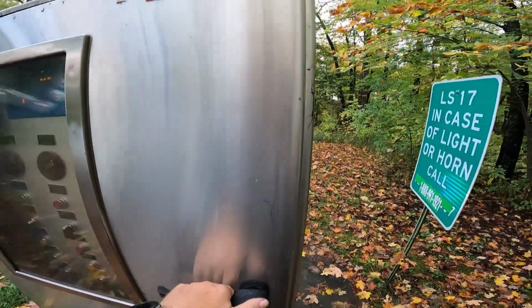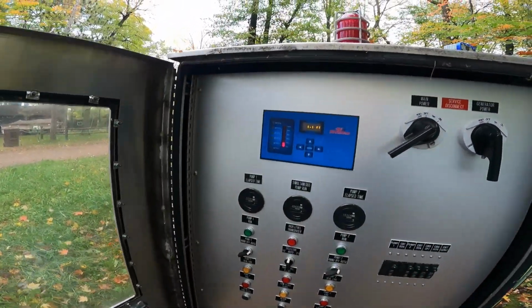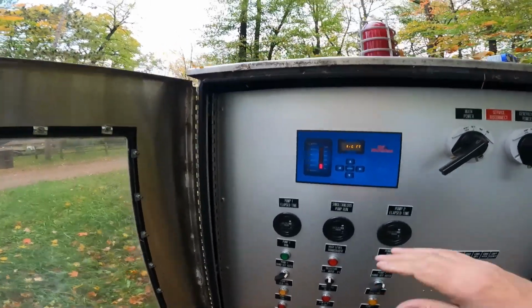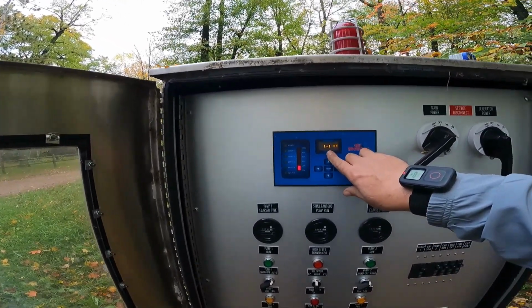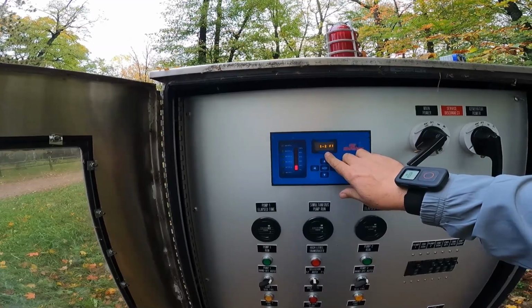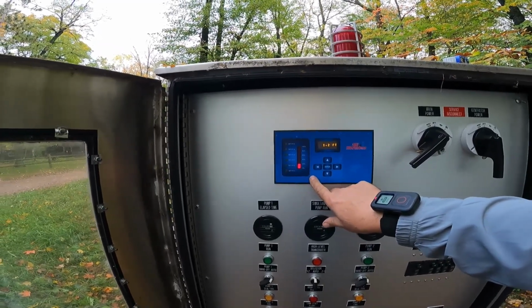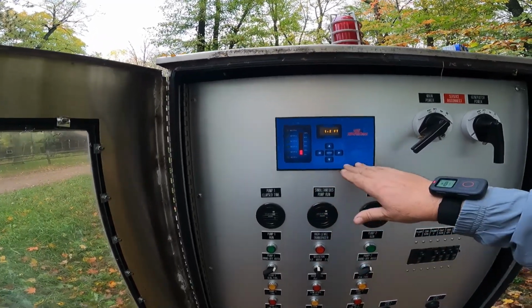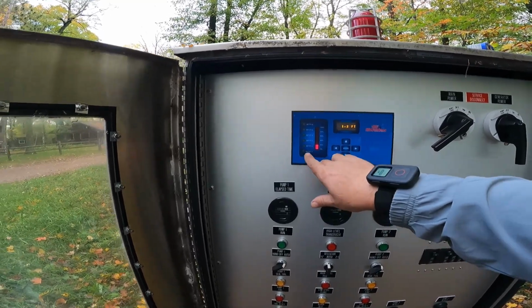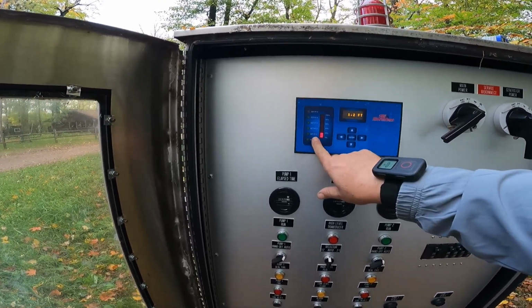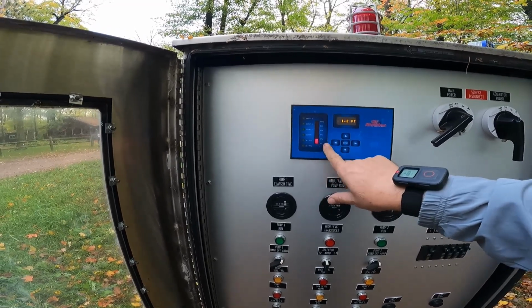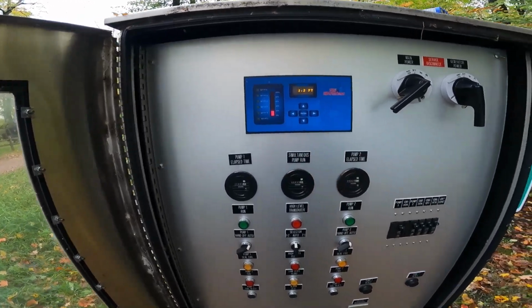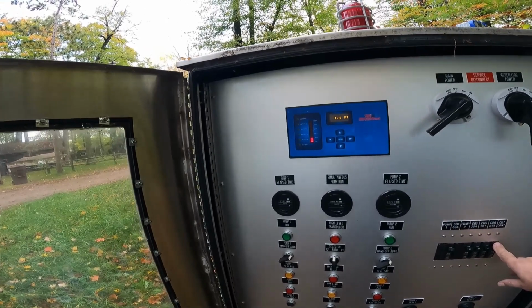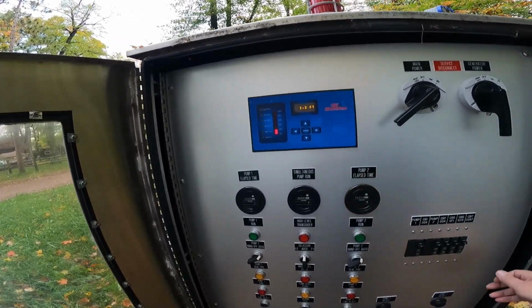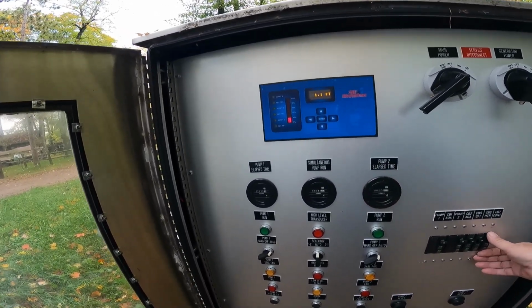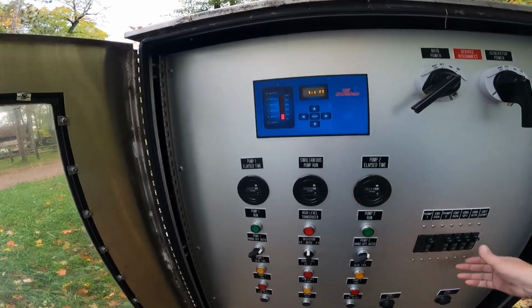I left the lock off last night, and what we're doing is watching our transducer number. The transducer is what tells the lift station how deep the water is in the tank. And then over here are our set points that tell the pump when to run and when not to run. So if you watch what I'm going to do here, you can see how this is bouncing around about 1.1, 1.2, and I can assure you there's more water in there than that.